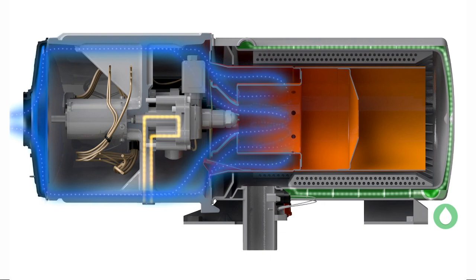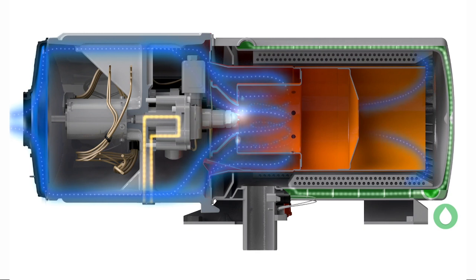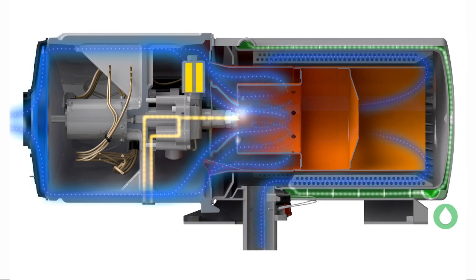You'll notice the fuel is making a short circuit, flowing right back out through the return line. After a short pause, the ignition leads fire while the fuel solenoid opens, allowing fuel to flow through the nozzle where it is atomized and mixed with the swirling air.